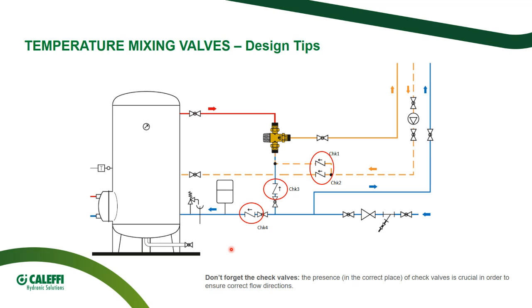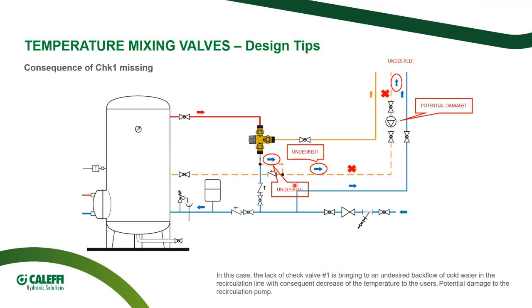So let's try a scenario. We forgot to install check valve number 1. Check valve number 1 is protecting the inlet of recirculated water in the cold water inlet of the mixing valve. What if I forgot it? I might have undesired inlet of cold water in the recirculation loop. If the system pressure is very high, it can go backwards, potentially damaging the recirculation pump and for sure reducing the temperature in the recirculation loop. So the users will not have the desired hot water temperature, so they will complain.